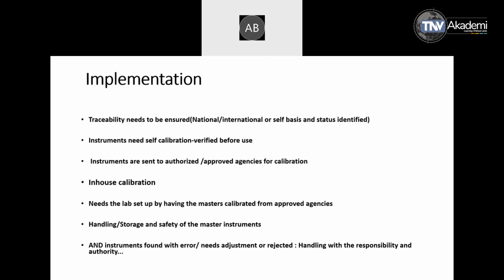They should collect the test certificates of their sample test certificate. They should collect their master calibrated test certificate. They should collect the national or international traceability certificate before accepting them as their approved calibrator or calibrating agency. Because in auditing we have seen sometimes that when we go into further details, we find things are missing. So when we talk of the team being trained enough, whoever is accepting the calibration certificate in the inspection department or QA department should be trained enough to understand all these requirements.